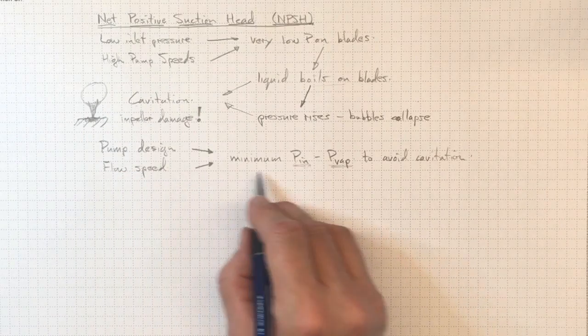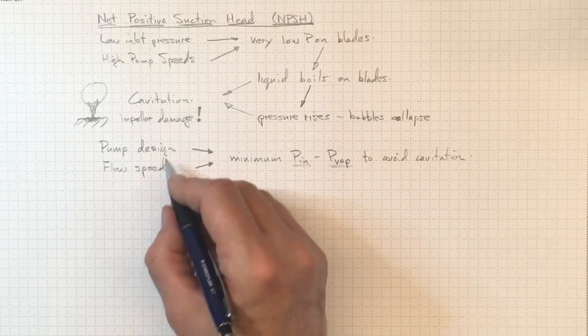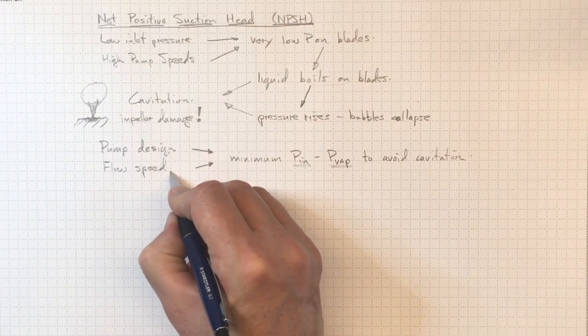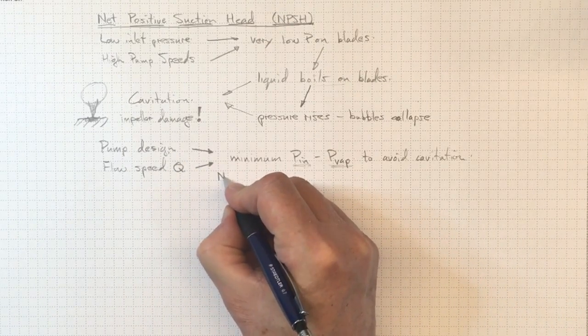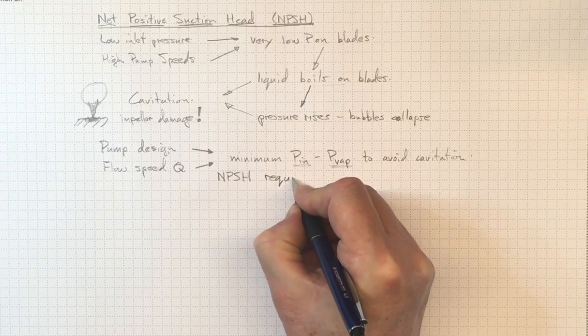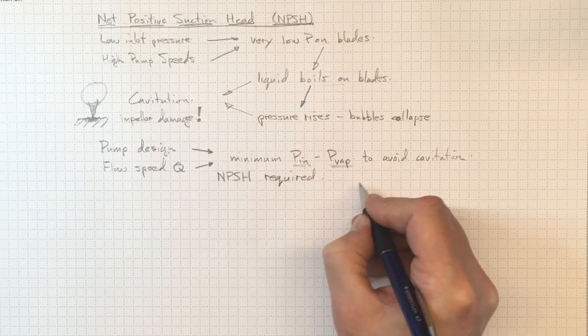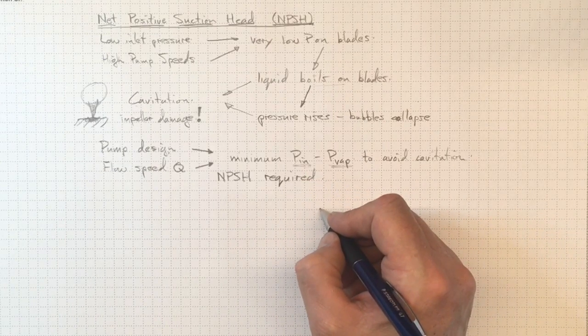The manufacturer will specify what this minimum is in order to avoid cavitation for a particular pump design at a particular flow rate as the NPSH, the net positive suction head required. And as long as you meet that requirement, then things will be okay.